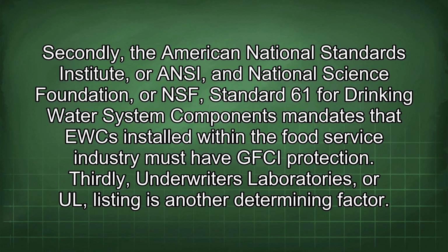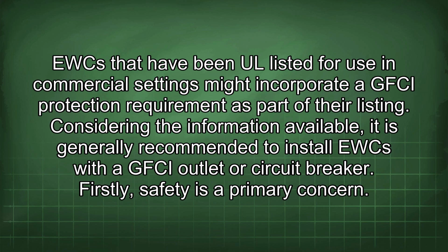Secondly, the American National Standards Institute, or ANSI, and National Science Foundation, or NSF, Standard 61 for drinking water system components mandates that EWCs installed within the food service industry must have GFCI protection. Thirdly, Underwriters Laboratories, or UL, listing is another determining factor. EWCs that have been UL listed for use in commercial settings might incorporate a GFCI protection requirement as part of their listing. Considering the information available, it is generally recommended to install EWCs with a GFCI outlet or circuit breaker.